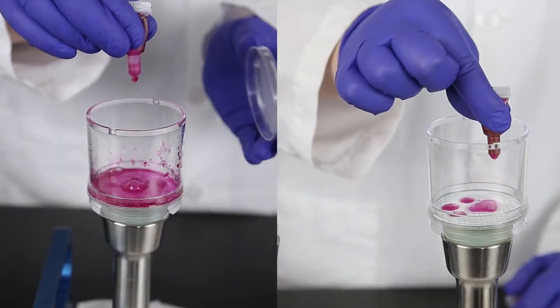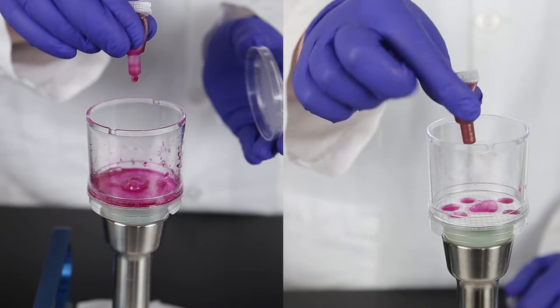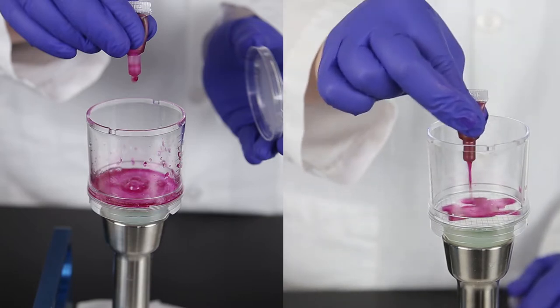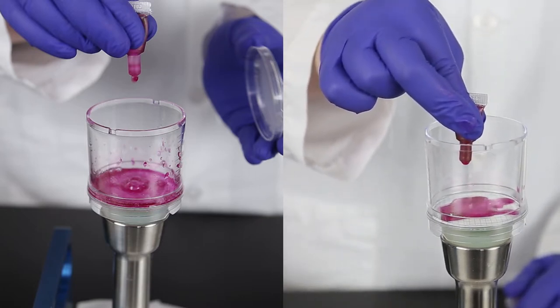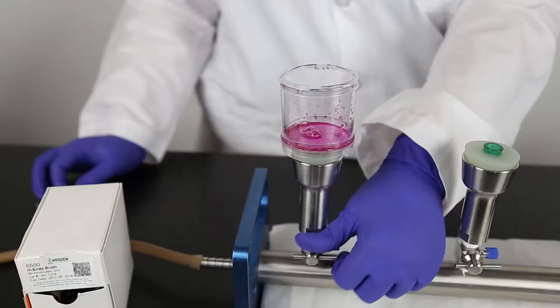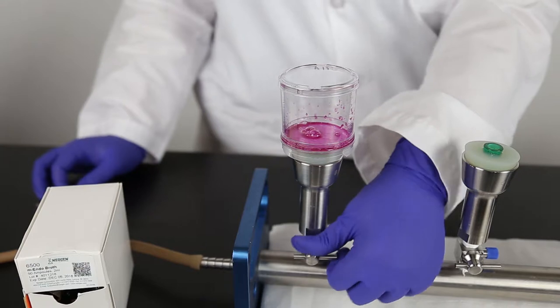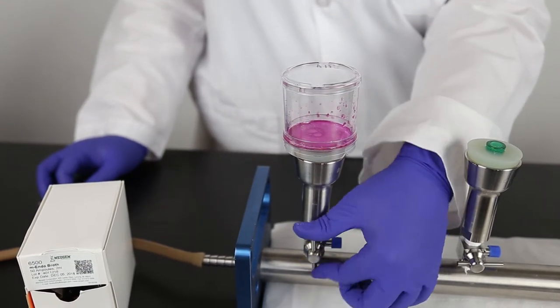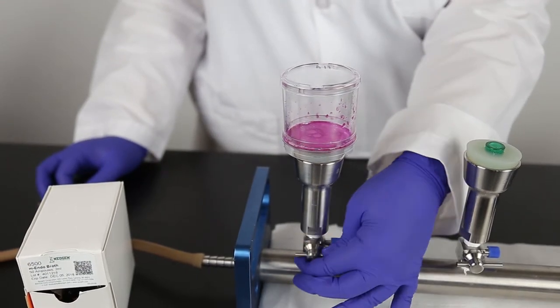Also, try to keep the ampule and your fingers out of the funnel area as much as possible, working just over the top of the monitor. When finished, replace the lid to prevent contamination. Open and close the valve quickly, just long enough to allow the vacuum pressure to draw the media into the pad beneath the membrane. Do not over-filter during this step.